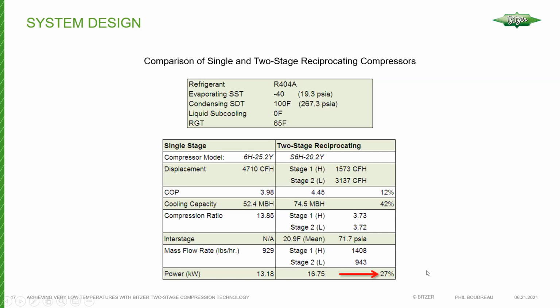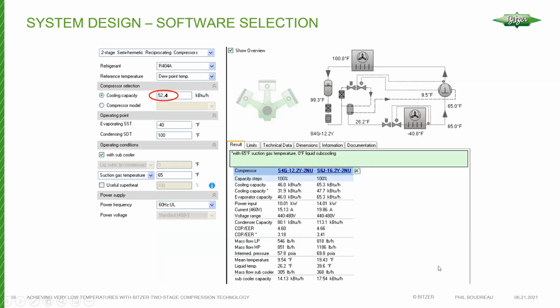If your load is only 52,000 BTUs or so, we don't really need a 74.5 thousand BTU compressor anyways, right? So in this case, we can go back to the software and select a compressor that's closer to the 52.4. And you'll see that you're definitely going to be dropping the compressor size. And then a decision's got to be made as to whether 46,000 is going to work or 65.3 thousand BTUs is going to work. But either way, now your power consumption is going to go down even further. Your efficiency numbers are greater. So these are the main benefits of applying a two-stage compressor.